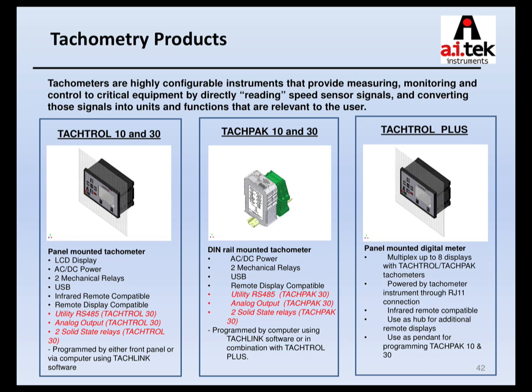They're not necessarily used in primary speed control, but they're used for backup as well. If you have a primary speed system, let's say on a turbine, you may want to be able to shut that equipment down, and a lot of those systems require a redundant system to their primary control in order to make sure that happens. So that's where the tach can come in as well, because it's not integrated with the main system at all, and it provides that safe control and safe shutdown.